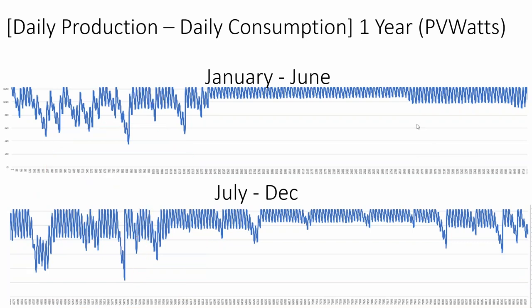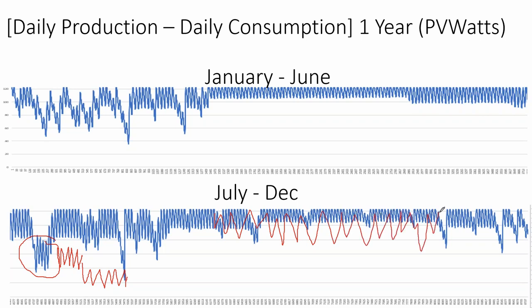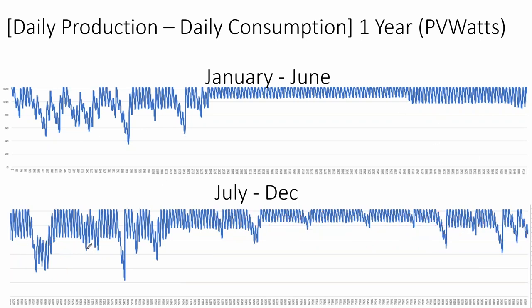Now, the customer could also say, oh, okay, I'm at a low end of my battery range, and so I need to not run my air conditioner so high. They could load shift and make some adjustments. But we also know that this battery is operating down at the bottom end of its absorb range and getting into that lower end bulk range, whereas here, we're operating at the top of the absorb range and into the float range and not really damaging our battery at all. So even though the system is sized to avoid generator use, we're still going to add a generator to the system.